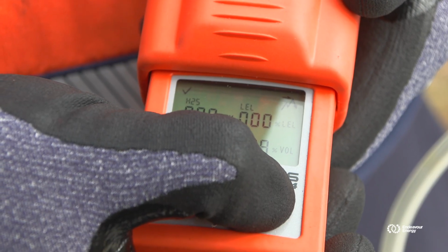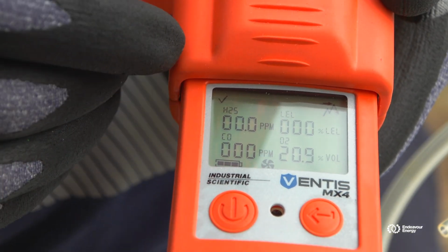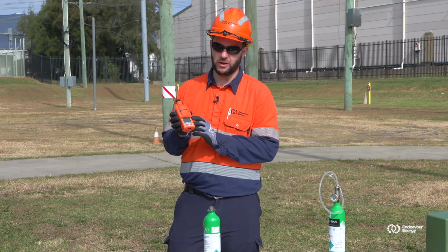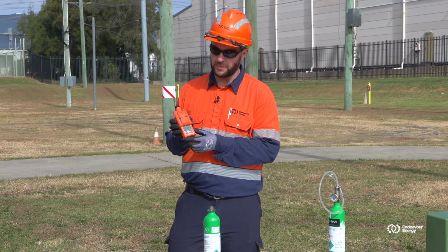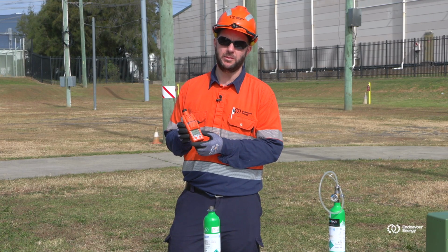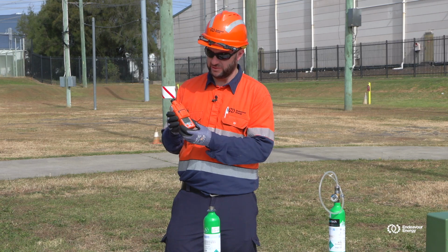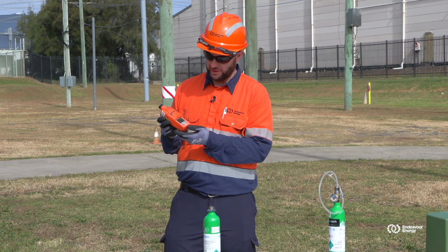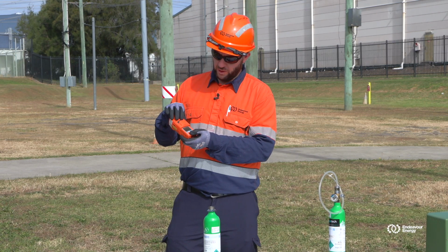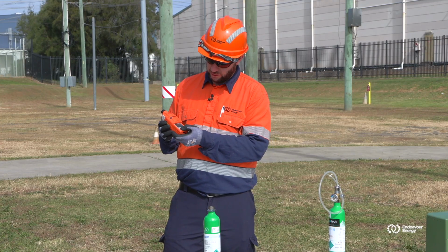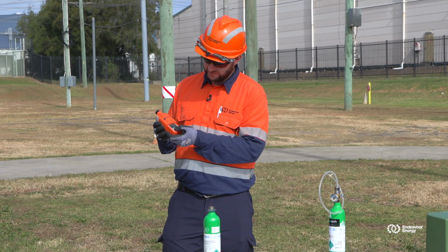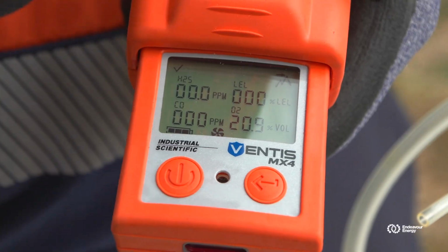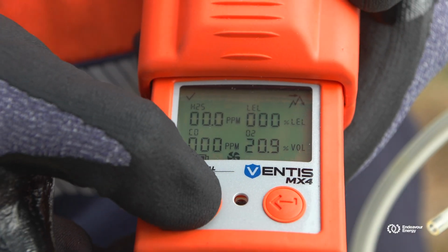Now that's clear, we have zeros for the hydrogen sulfide, zeros for the lower explosive limit, zero for the carbon monoxide, and we have a rating of 20.9% for the current rating of oxygen, which we're displaying in the fresh air. Before we go to use the unit now, we're going to scroll back to our current fresh air rating. So we're going to press the power button, scroll back through, and there we have a rating here.